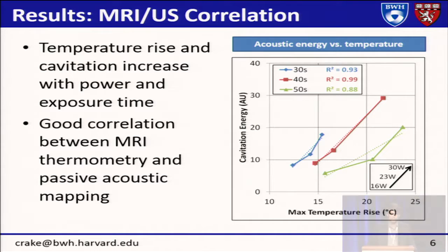We then looked at how these two modalities compare in a parametric study. So we varied both the ultrasound power input and the duration of the exposure. And as you might expect, as you treat for longer or you increase the ultrasound power, then both your maximum temperature rise and your maximum cavitation energy increase. And the two are well correlated, pretty linearly as well.